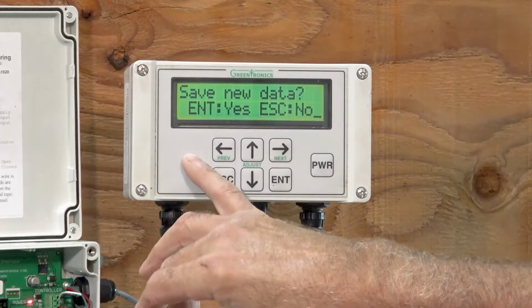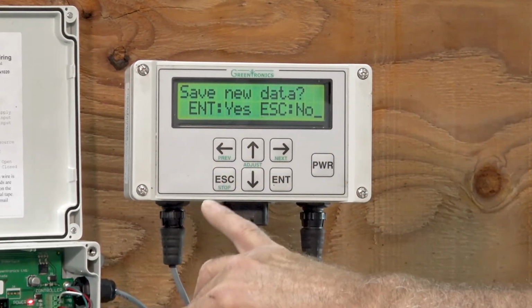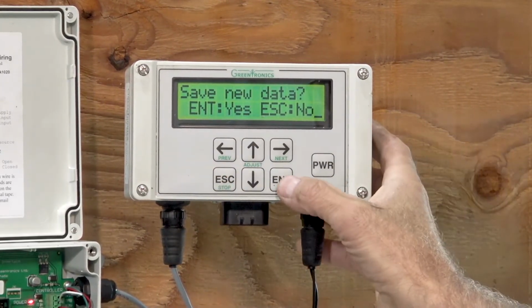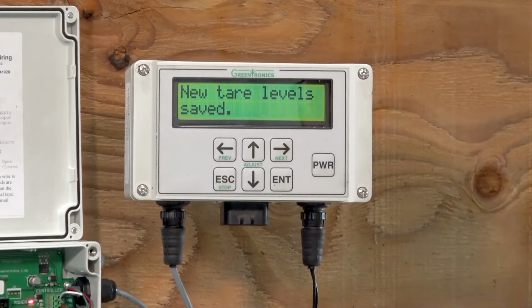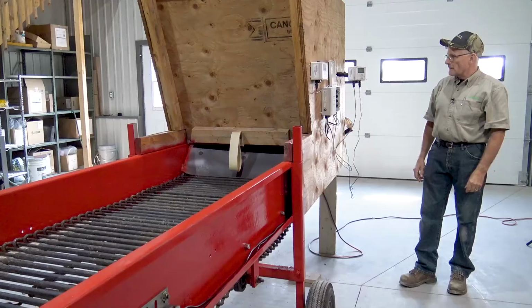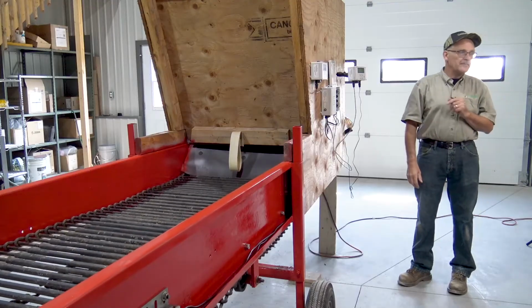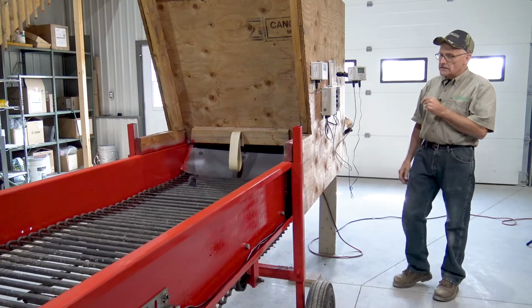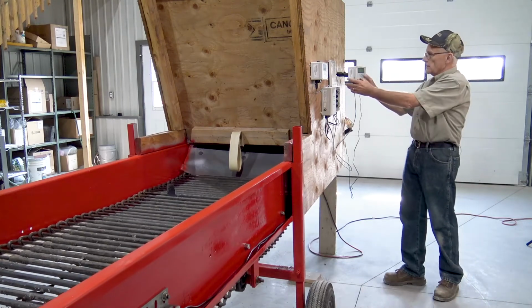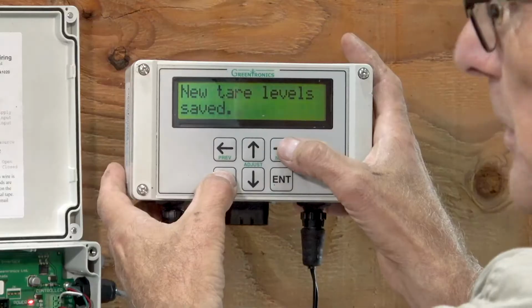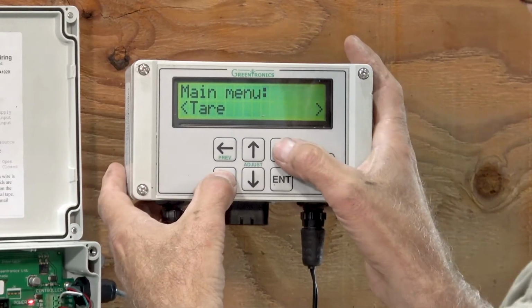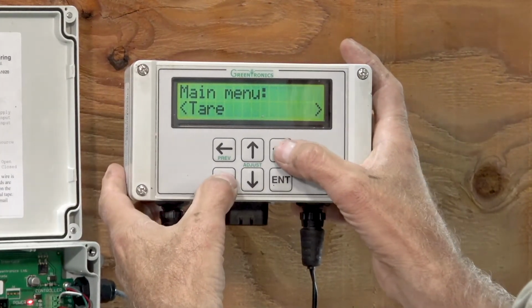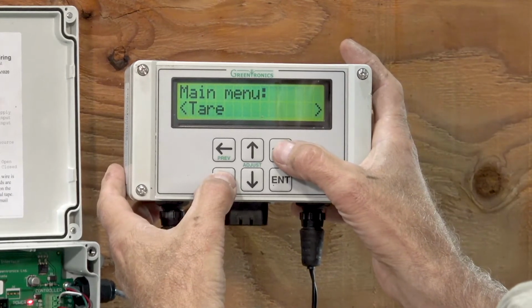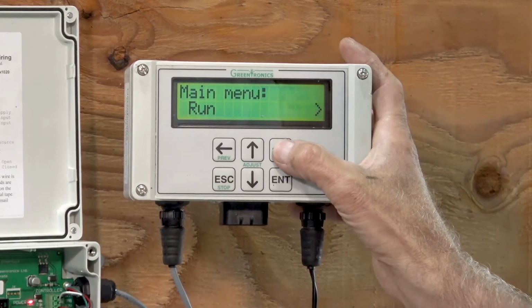Good, so it asked me save new data. I like the new data, so we're going to save it. Enter. New tare level saved. So now the next step, also very important, is to confirm that you actually have a good tare calibration. We're pretty sure we do, but you should check. And there is a check for that in the test menu. So we're going to the test menu.